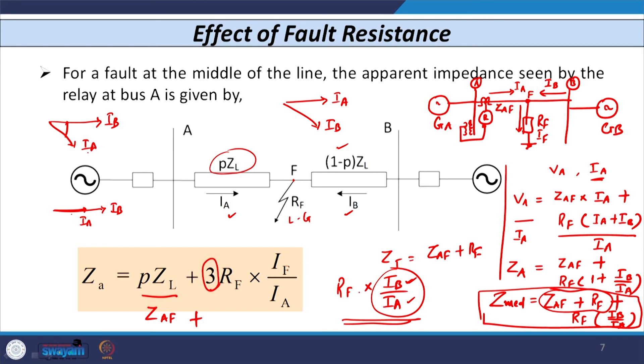So, this is very important that we consider the pre-fault power flow, because as I told you, the phase angles of the two sources connected at bus A and bus B are different. That is why both the currents IB and IA are not in phase. So, not only the real part of the measured value, but the imaginary part of the measured impedance is also affected because of the fault resistance. So, the measured inductive reactance, that is the imaginary part, is also affected.